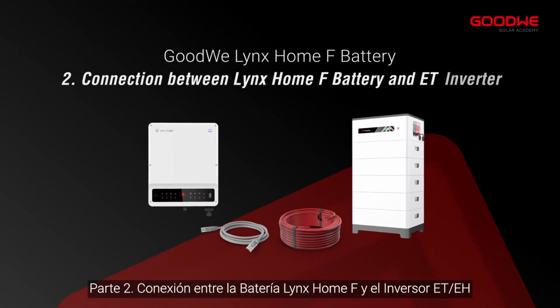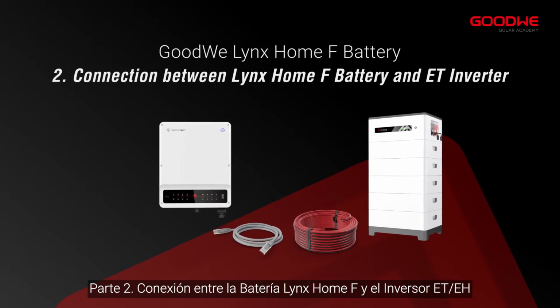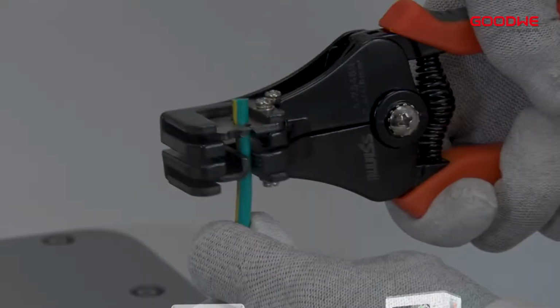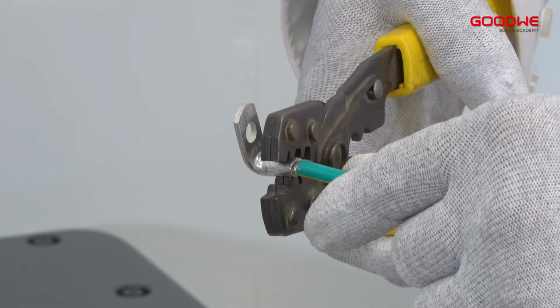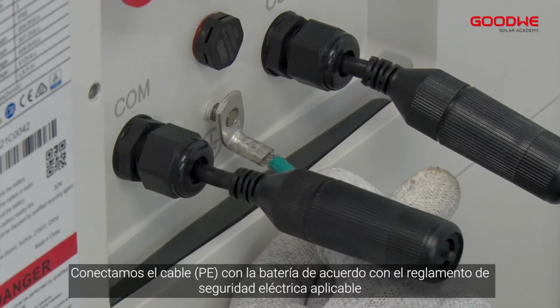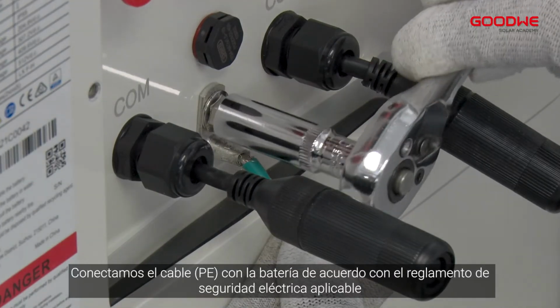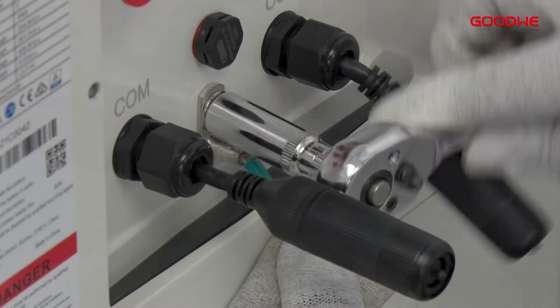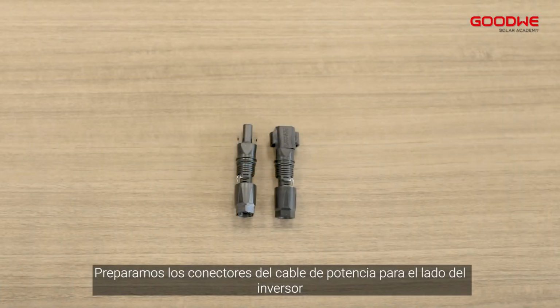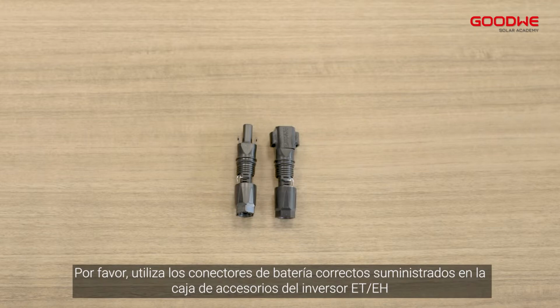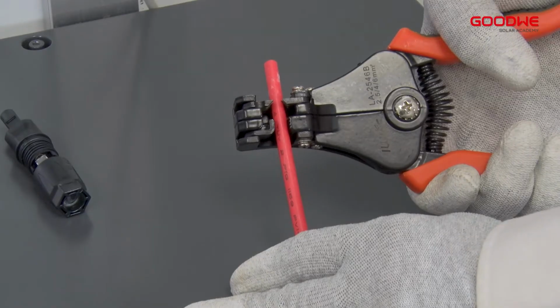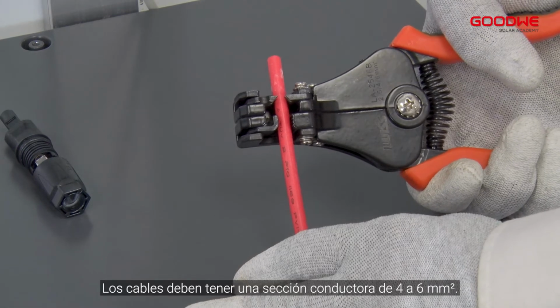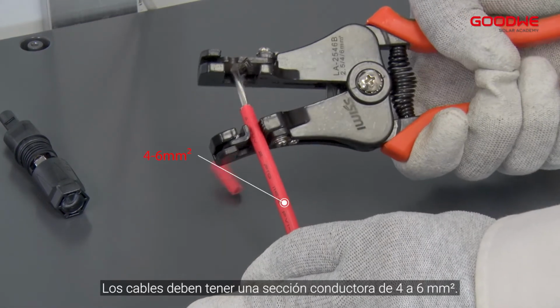Part 2. Connection between Lynx Home F battery and ET inverter. Strip off the wire. Crimp the PE cable. Connect the PE cable to the battery according to local safety requirements. Make power cable connectors for the inverter side. Please use the right battery plugs in the accessory box of the ET inverter. The cables should have a conductor cross section of 4 to 6 square millimeters.